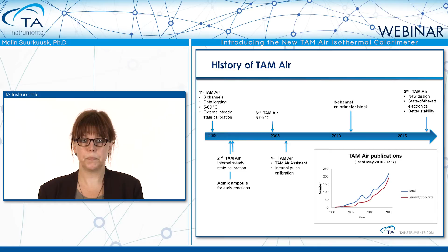In 2012, we introduced the 3-channel TAM Air for allowing bigger samples such as concrete samples. So you have 3 channels up to 125 milliliter. And now this year, we introduced the 5th generation TAM Air. It's a new design, state-of-the-art electronics, and gives us much better stability of the baseline. We can also see on the TAM Air publications, starting in 2000 up to May this year, that we have over 1,200 publications for TAM Air, and over 900 of these are for cement and concrete research. So that's the main application area of the TAM Air, even if we see use in other fields as well, which I will mention when I come to the application parts of the presentation.